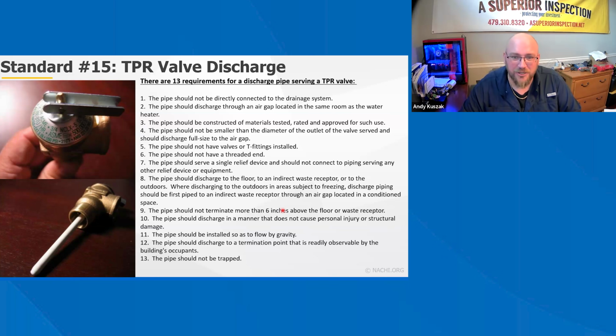Or you have an animal, or say the temperature pressure relief valve extends to the outside and it terminates more than 6 inches off the ground, and your dog is over there, you fenced off that part of the house, and now that's where your dog hangs out, and that TPR valve pops off and your dog is sitting right next to it. Now you have to take your dog to the vet because they've been burned and scalded. So those distances are very important.